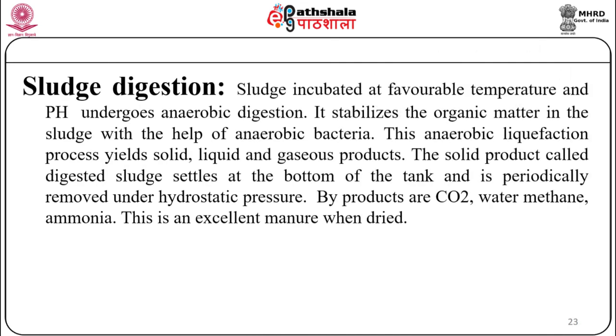Sludge digestion involves sludge incubated at a favorable temperature and pH undergoing anaerobic digestion. It stabilizes the organic matter in the sludge with the help of anaerobic bacteria. This anaerobic liquefaction process yields solid, liquid, and gaseous products. The solid product, called digested sludge, settles at the bottom of the tank and is periodically removed under hydrostatic pressure. By-products include CO2, water, methane, and ammonia. The dried digested sludge is an excellent manure that can be used for agricultural purposes.